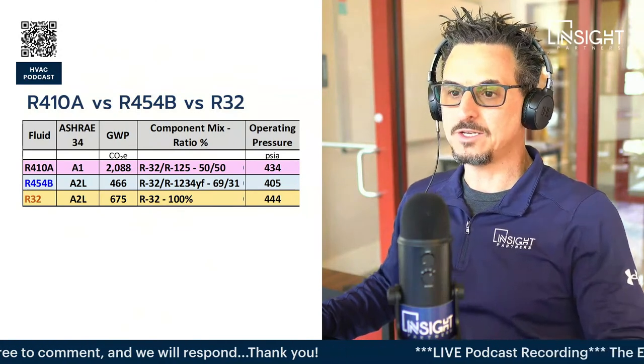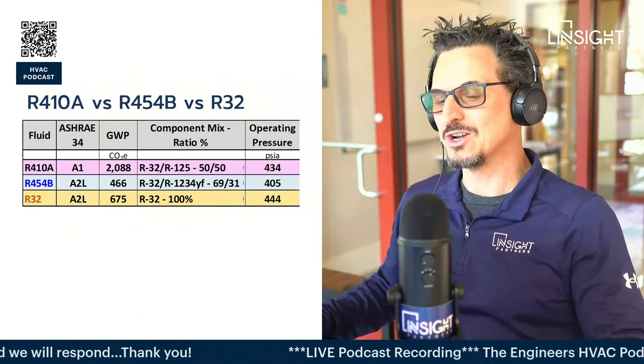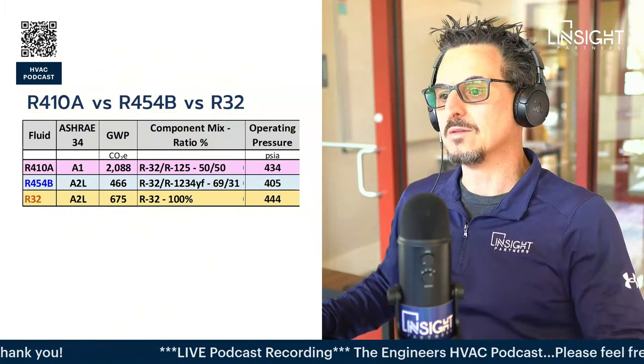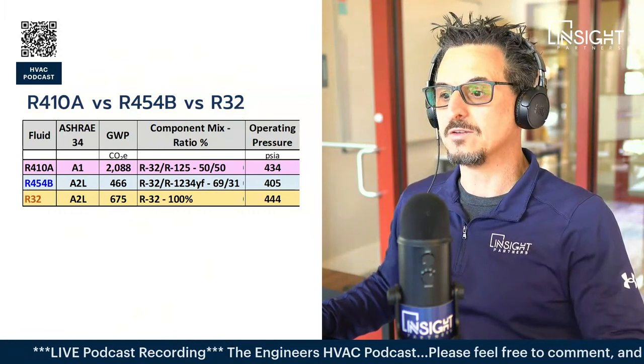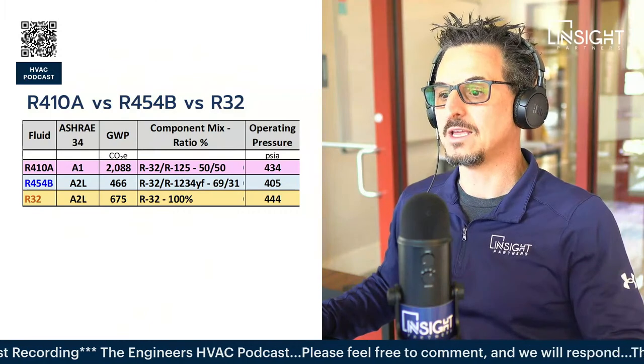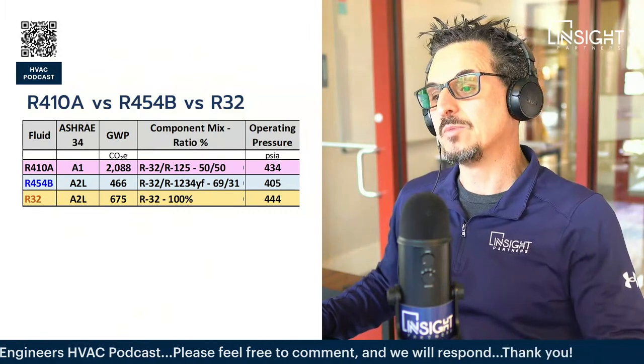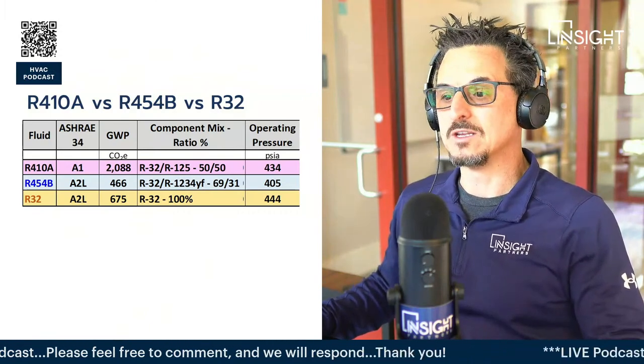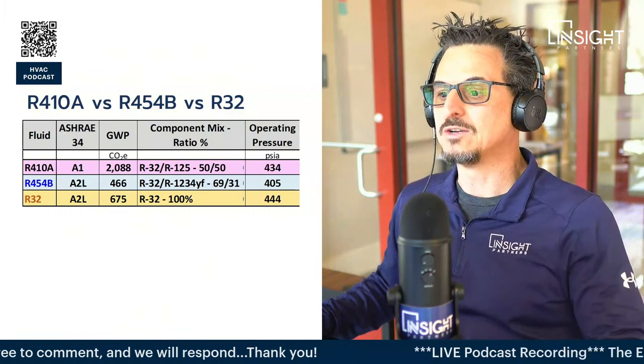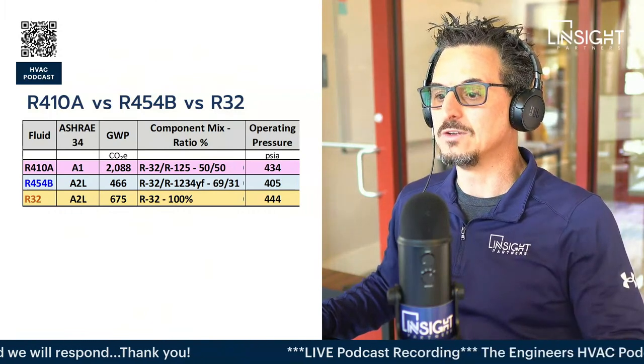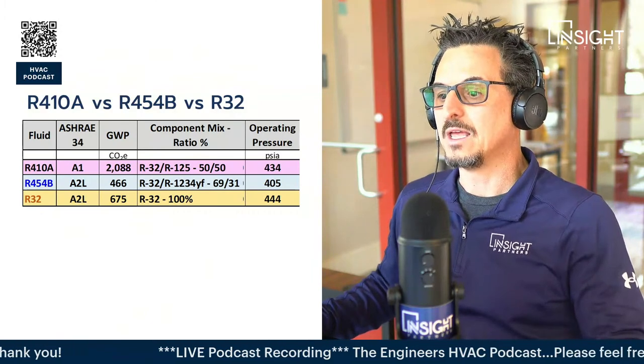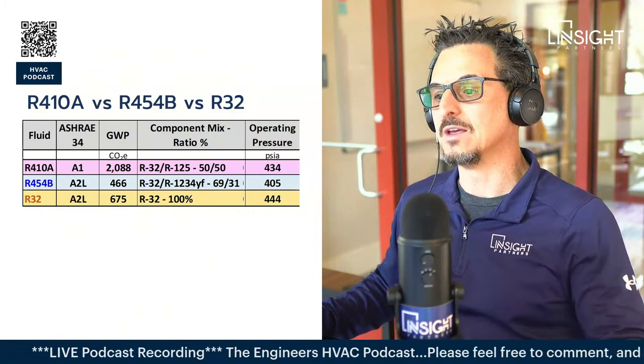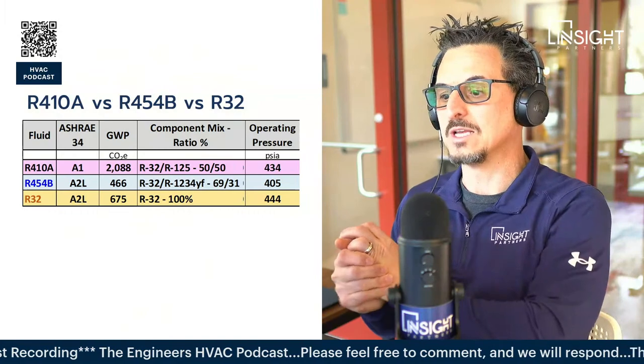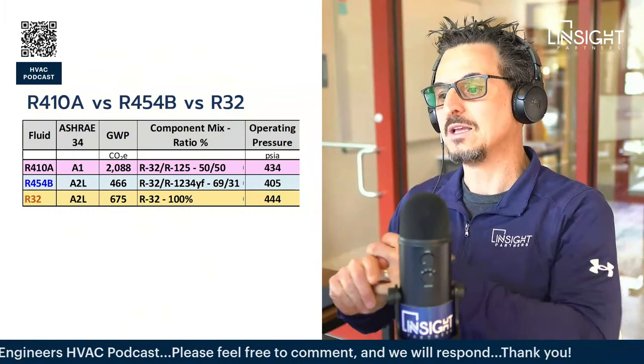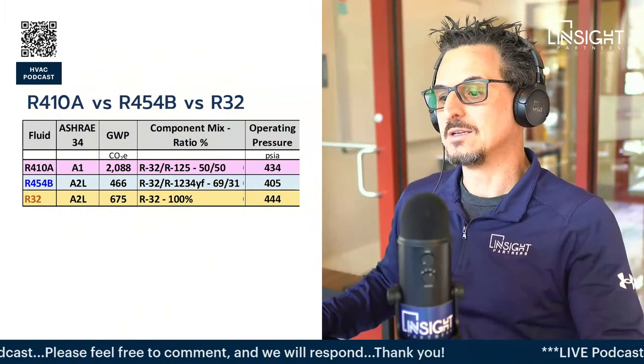Okay, key considerations when determining which refrigerant you're going to use as a manufacturer: safety is always an essential factor. The fact that the two leading candidates are flammable per ASHRAE 34 makes the transition even more critical. The A2L designation is a relatively new designation for ASHRAE, created specifically to denote differences between refrigerants with high burning velocity and ignition characteristics.